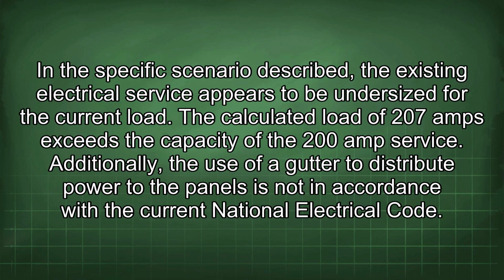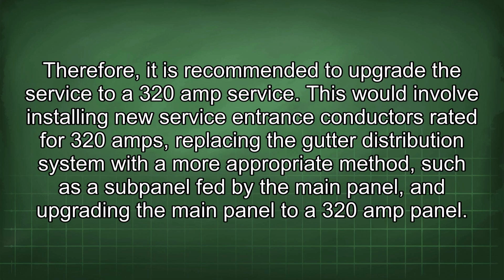In the specific scenario described, the existing electrical service appears to be undersized for the current load. The calculated load of 207 amps exceeds the capacity of the 200 amp service. Additionally, the use of a gutter to distribute power to the panels is not in accordance with the current National Electrical Code. Therefore, it is recommended to upgrade the service to a 320 amp service.